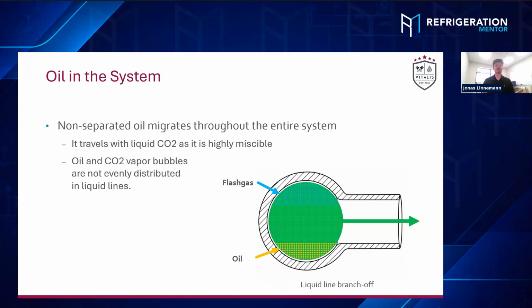It would still happen. That's also why we still go off the side here in the liquid lines, even if we deliver these liquid manifold stations or the liquid suction manifold stations for individual loops. But the effect will be lower, basically. Definitely. It's lower just on the individual circuits versus the loops.